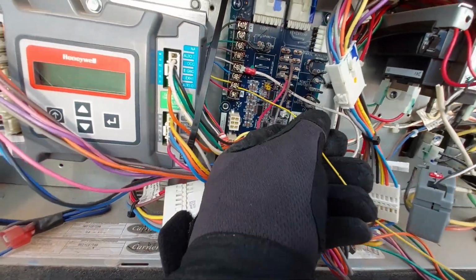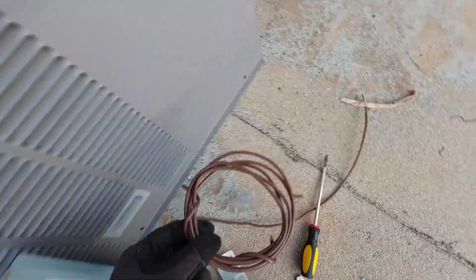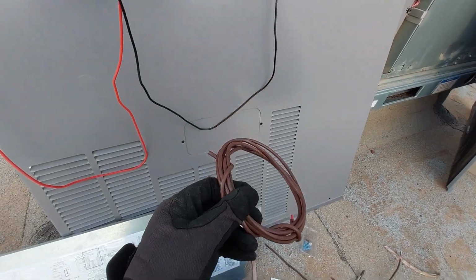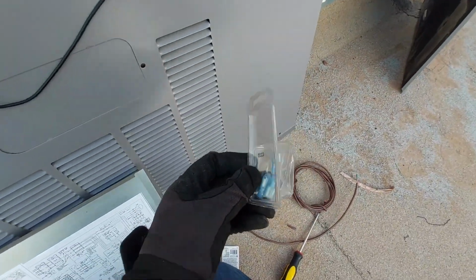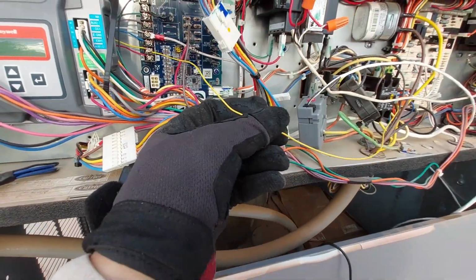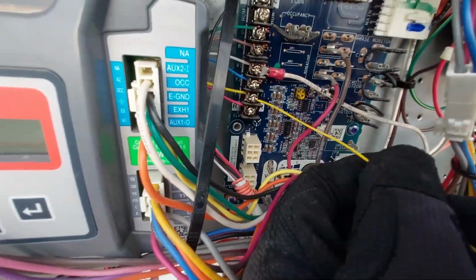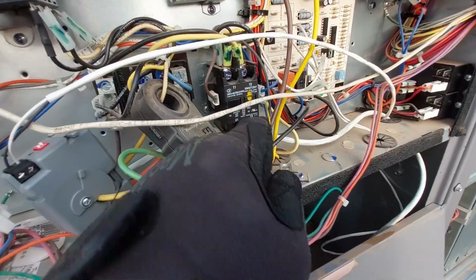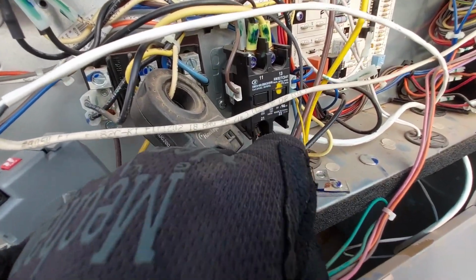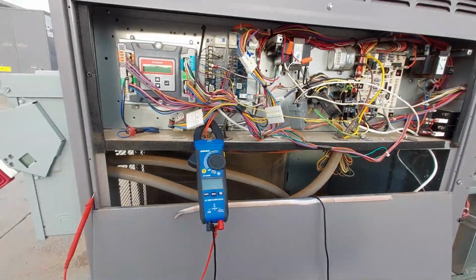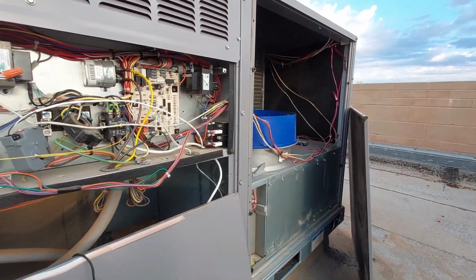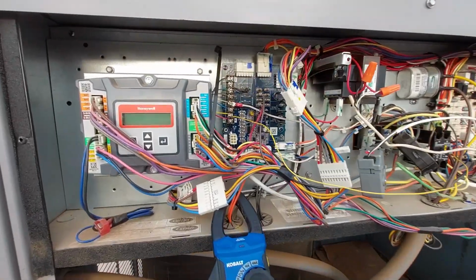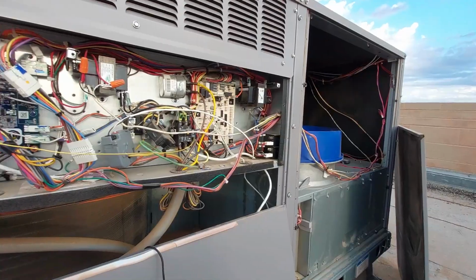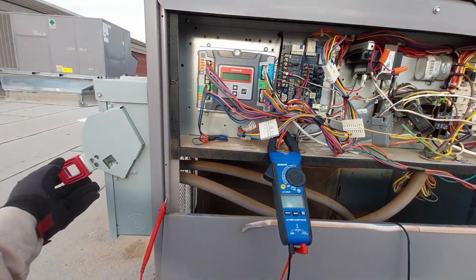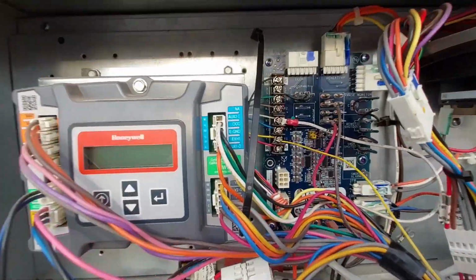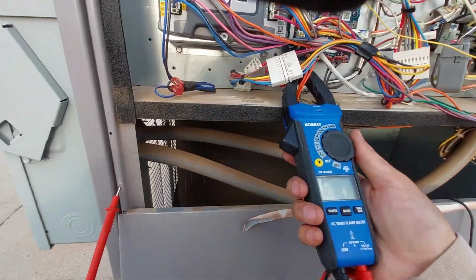Alright, so here's what I got going on. I always have a little bit of thermostat wire in my backpack, and I got some spades too. So I took the yellow wire out of there and I made a jumper from Y1 all the way to my contactor on the 24 side. So if I turn on this disconnect, the contactor should push in because I was getting 24 volts. I don't think that condenser fan was going to turn on, so we'll see. Let's see here.